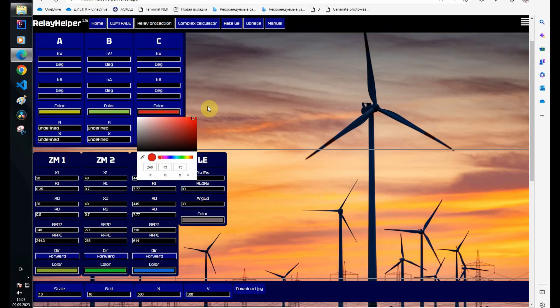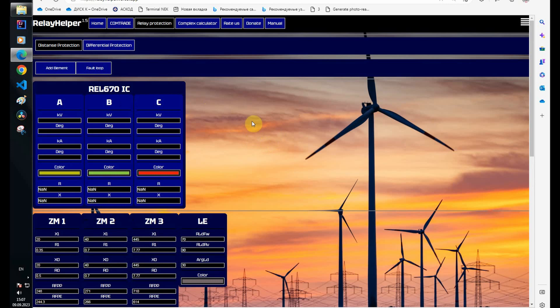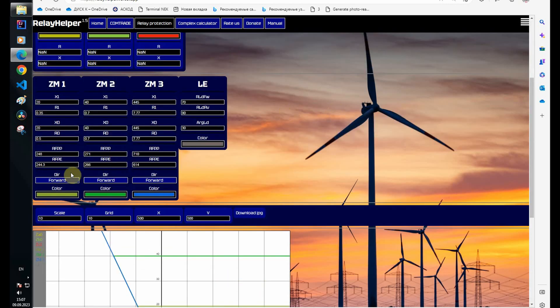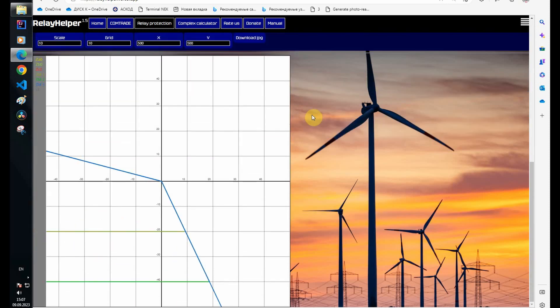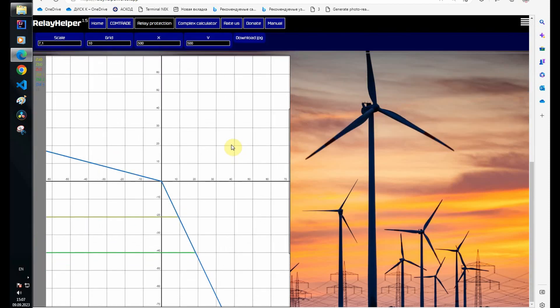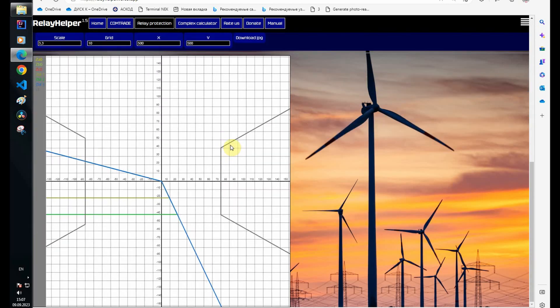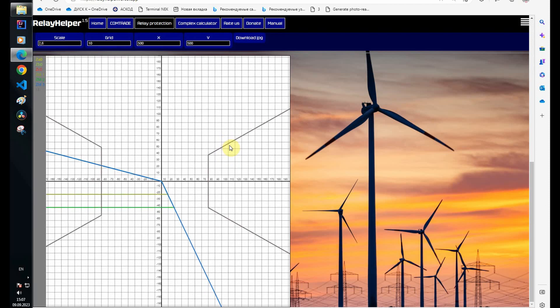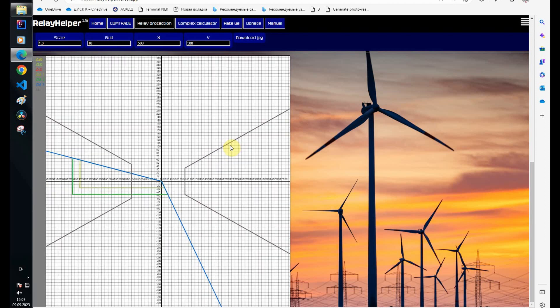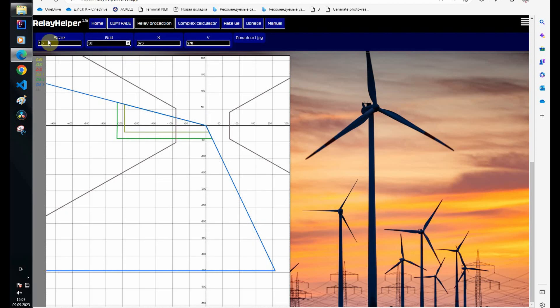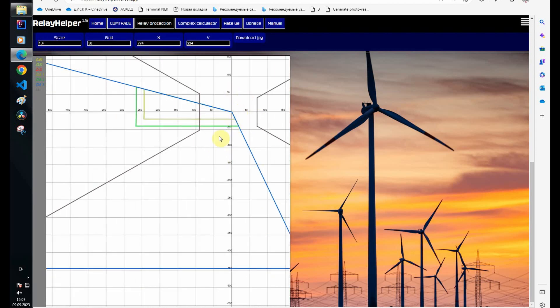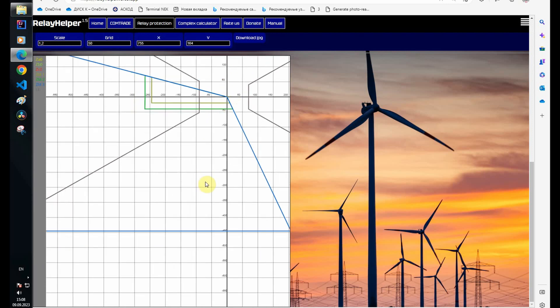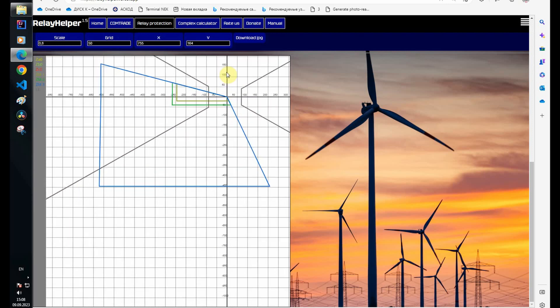To display zones, I need to select a short circuit loop. In this case, the loop is phase to earth. I'll change the impedance grid. The third zone is simply huge.